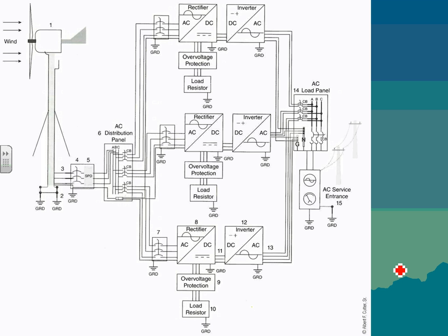So what they do is use multiple inverters. They kind of slice it into thirds. They take the power here because it's bigger than what one single inverter can handle, and collect it into a panel. That's easy, right? You split it into three chunks, land each third on one inverter rectifier system, and then bring it back into AC as a three-phase system, like you can see. So why would you do something like this? Because you utilize the available inverter size.